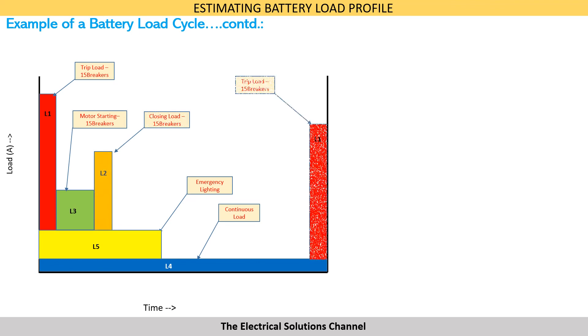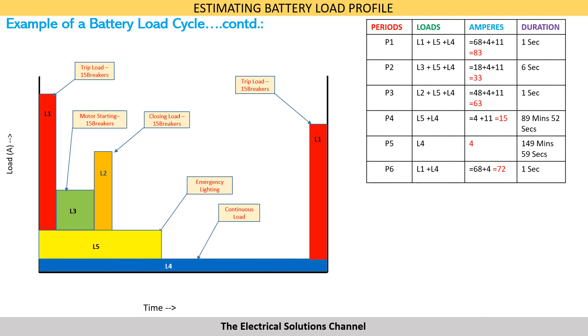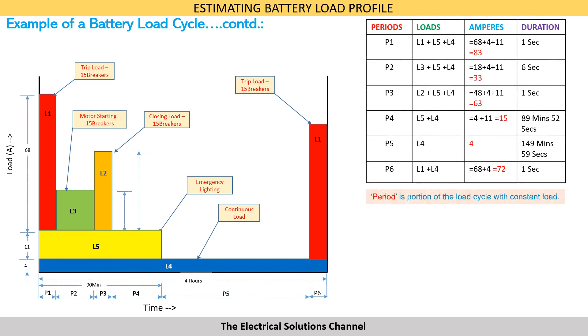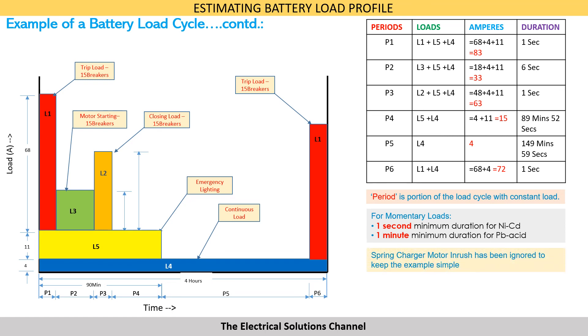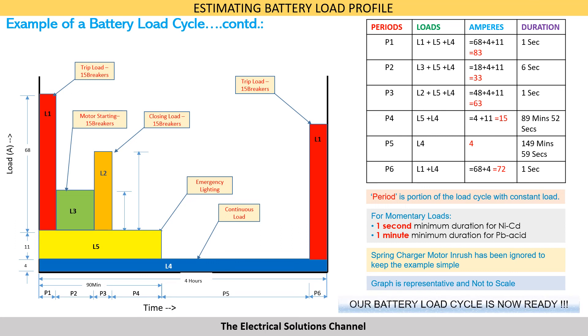We can also tabulate the loads to depict the total load at any given instant in the battery load cycle. The battery load cycle is divided into various periods, where a period is the portion of the load cycle with constant load. For momentary loads, 1 second shall be the minimum duration for nickel cadmium batteries, while for lead acid batteries the duration is kept as 1 minute. Spring charging motor inrush has been ignored to keep the example simple. With this, our battery load cycle is complete and ready for use.